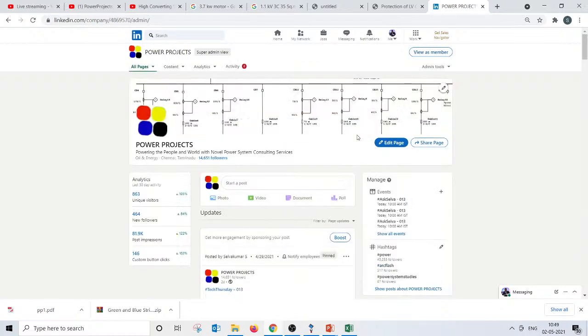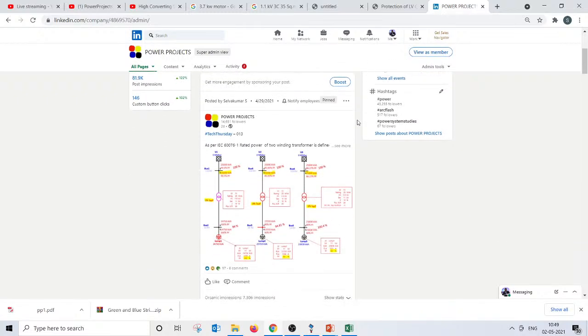Yes, Praveen, that is not really the right answer. Transformers are rated in kVA because copper loss depends on the current, iron loss depends on the voltage, and it doesn't depend on the power factor. That might be what we learned in college, but that's not really an ideal answer. Transformers don't have any independent constraint on real and reactive power, and the capability curve of the transformer is a circle, and that's the reason why transformers are rated in kVA.